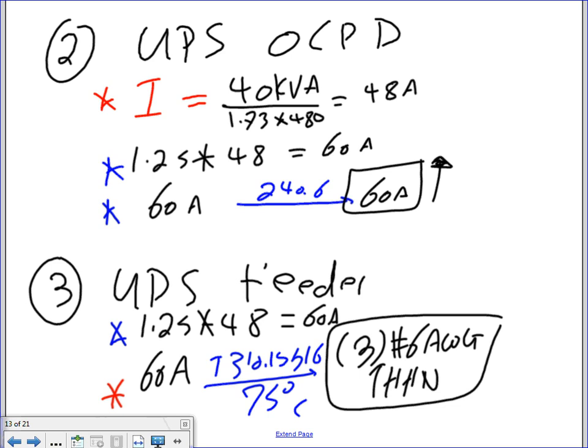Now, Karen, I found the actual size of the UPS. I put a 60 amp circuit breaker in the main panel, and I pulled 3 conductors, number 6, from that panel into the UPS. Now the primary side of the UPS is done. Now I'm going to go out of the UPS to the PDUs.